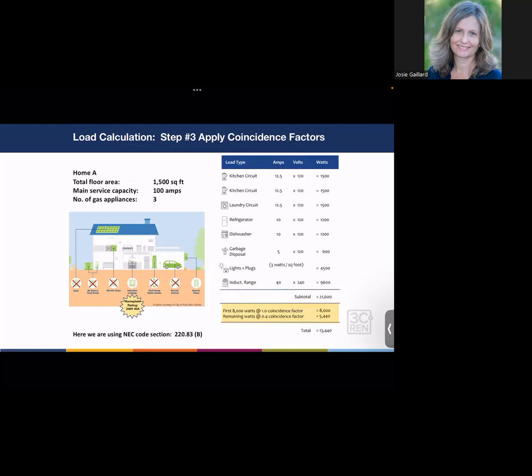Moving ahead, the code tells us to apply different coincidence factors. So the first 8,000 watts of load in the home gets a coincidence factor of 1.0. So we just multiply 8,000 times 1, which is 8,000. The second, all of the remaining watts in the home, the code tells us we can apply kind of like a derating factor of 0.4. So only 40% of those remaining watts get applied to the panel amps.